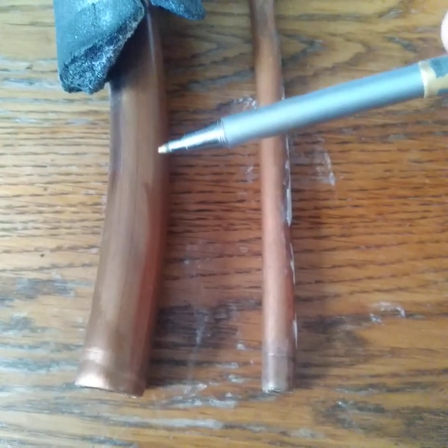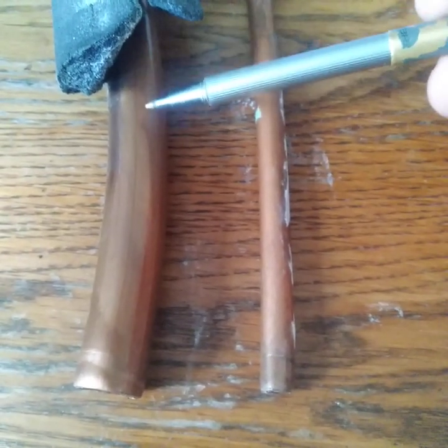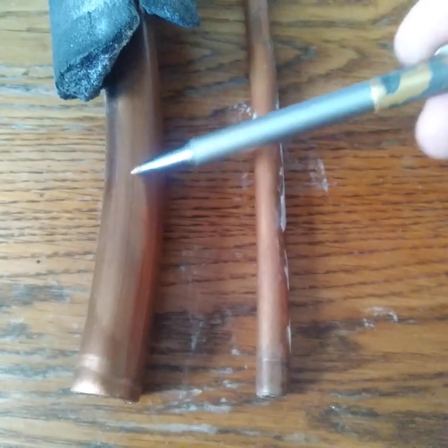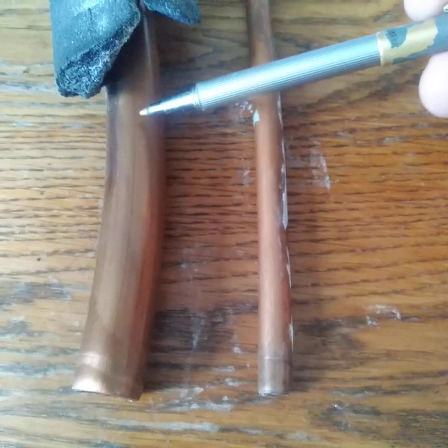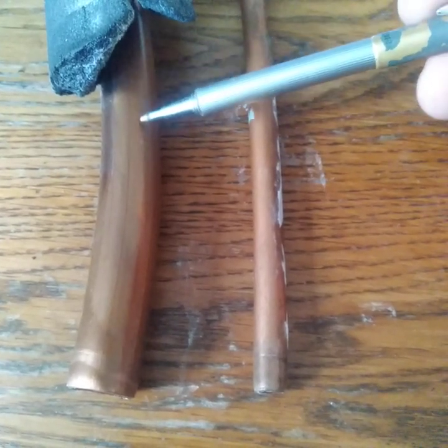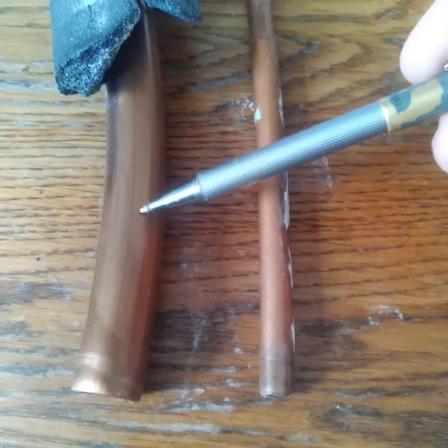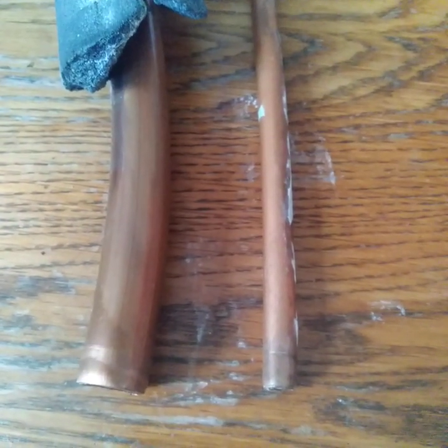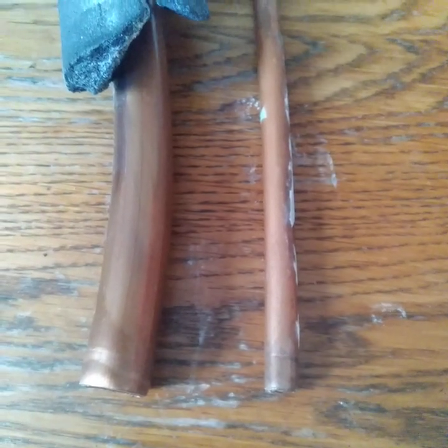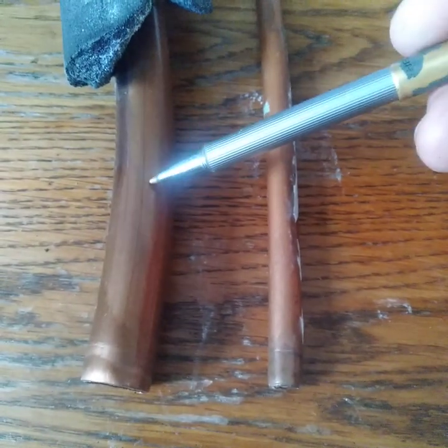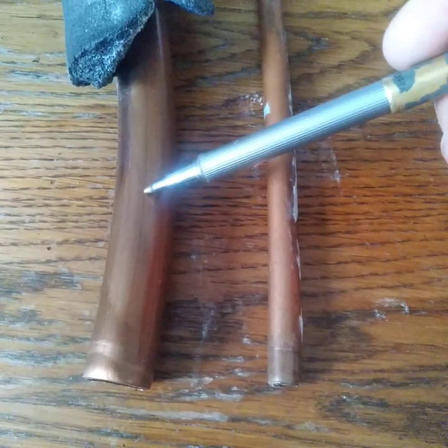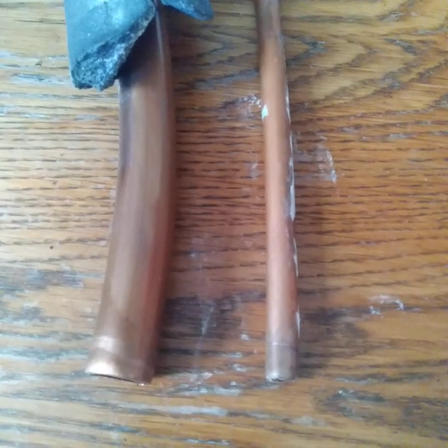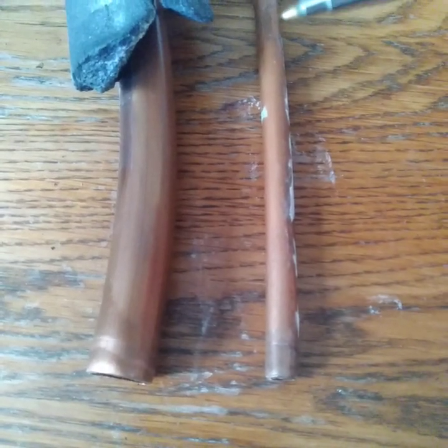So this particular side would come in, go through the evaporator, and then come out and go to the compressor as a low pressure vapor. And a compressor, as the name speaks, compresses. It compresses a low pressure vapor into a high pressure vapor as it exits the compressor.